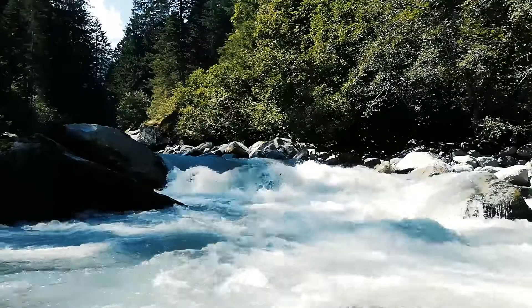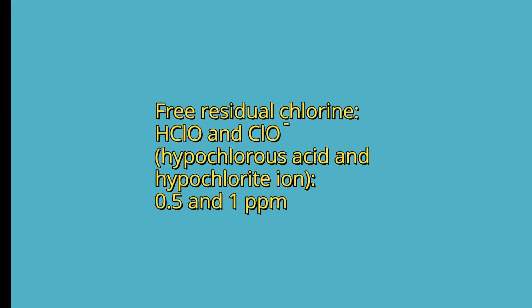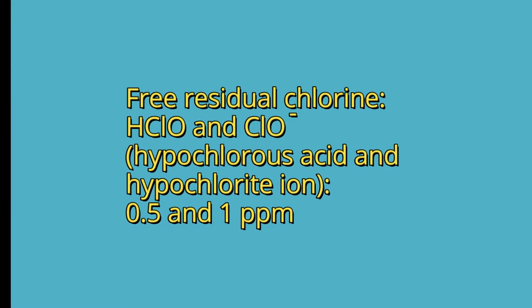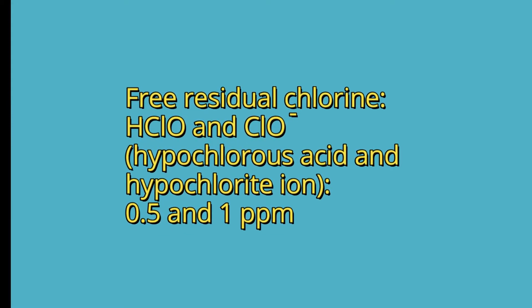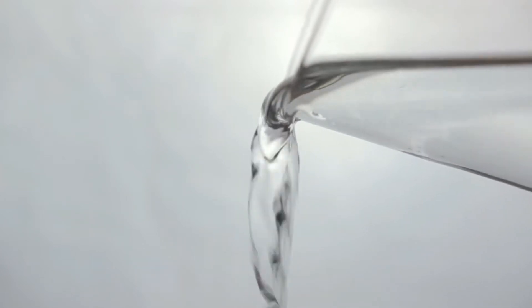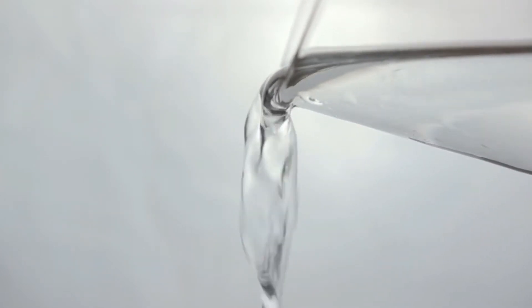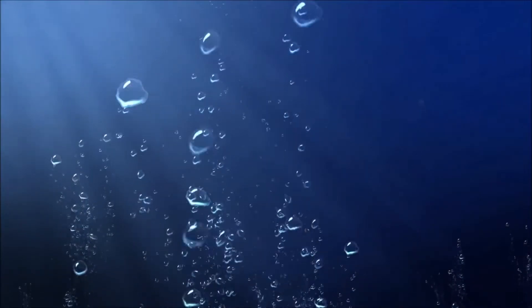After water treatment, the free residual chlorine content — hypochlorous acid and hypochlorite ion — must be between 0.5 and 1 ppm to prevent further contamination of water along the route to consumers. Knowing the active chlorine content that remains after chlorination allows guaranteeing its microbiological quality. After disinfection, the water must contain the minimum content of free residual chlorine.